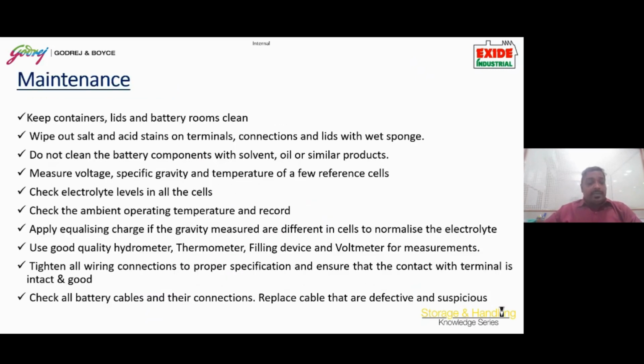Going further on maintenance, the containers and lids in the battery room should be clean, because the battery room itself will be a very corrosive environment due to the evolution of hydrogen gas and electrolytes. Acid stains should be cleaned from the battery surface. A regular cleaning of the terminals should be done. But while cleaning, please ensure that the positive and negative materials are not brought in contact by any external tool or equipment or even with a hand.